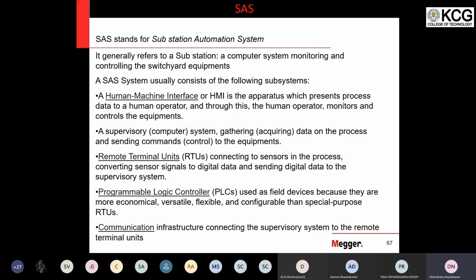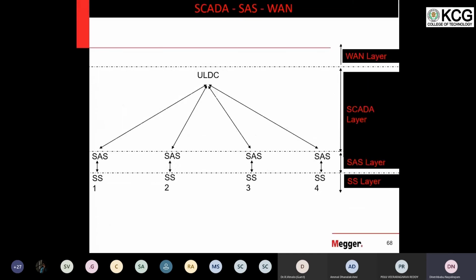Immediately it reads the current and shows it on our screen. Now what happens? You have pressed the button read current and it is giving you that information. But without you pressing the button, if all the data is already pulled by that system and streaming continuously, and on the screen you are able to see everything, then it's an example of an automation system. This is the difference of the different layers: substation layer, substation automation system layer, SCADA layer, wide area networking layer, WAN. And above this we have synchrophasors, WAMPAC.